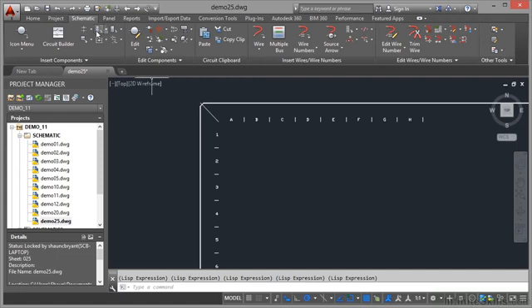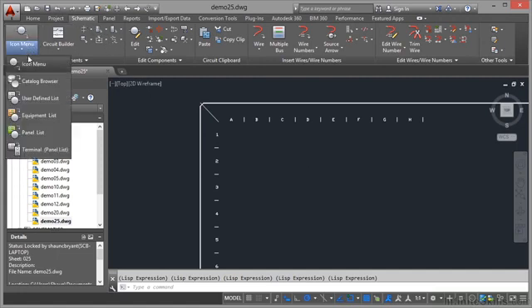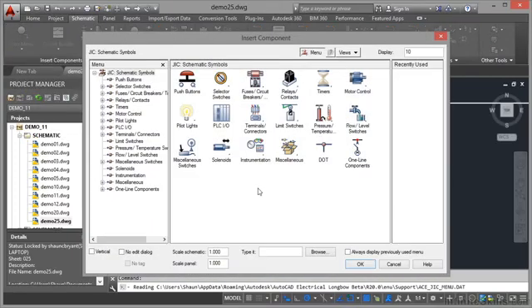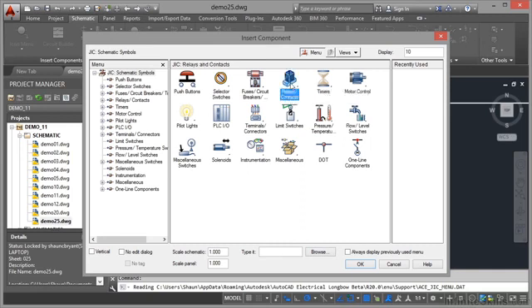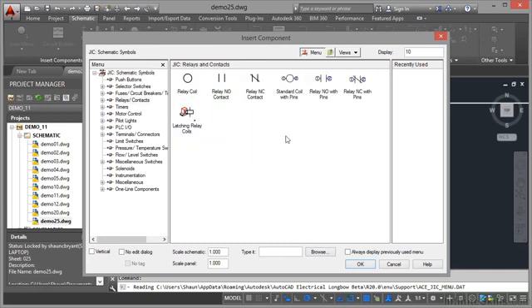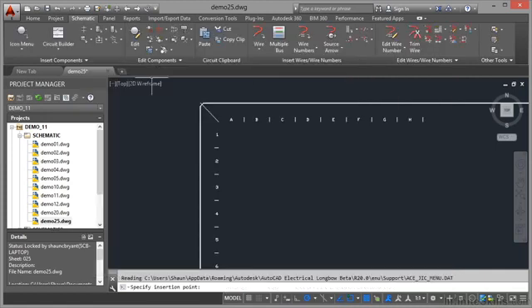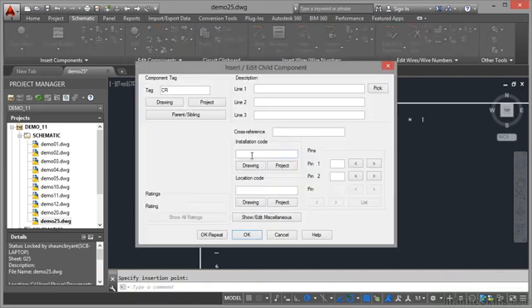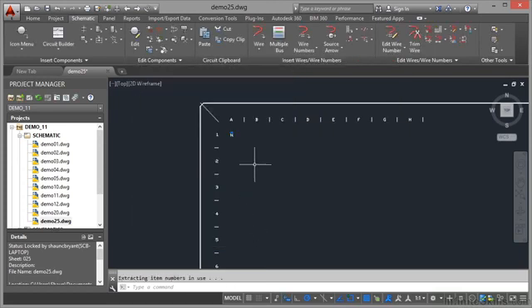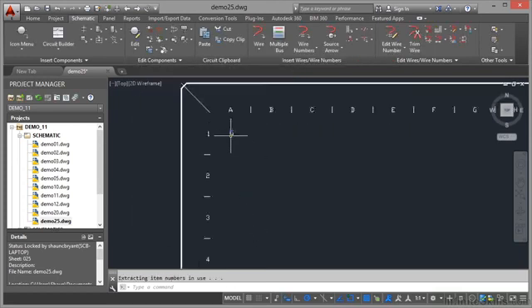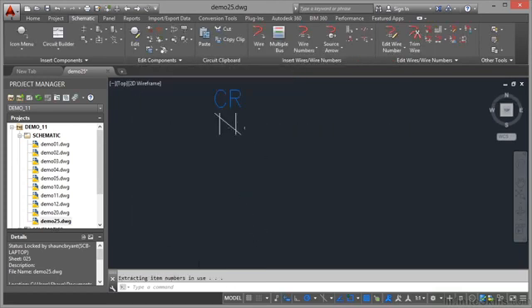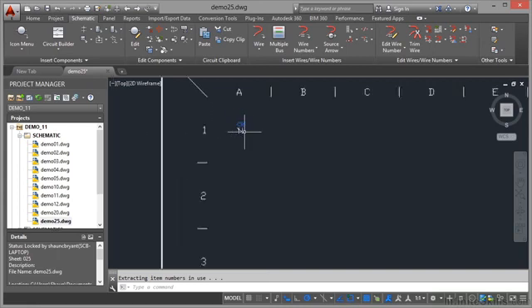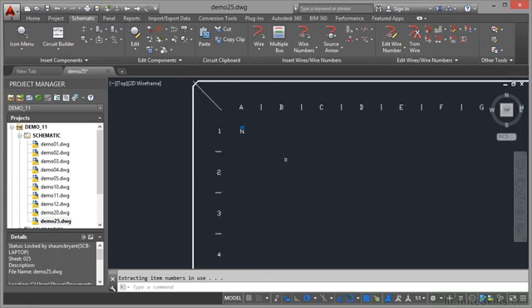I'm going to go to the schematic tab on the ribbon and then click on the icon menu and this will bring up all of the icons, the schematic symbols that I can place inside my drawing. So let's go for something simple like a relay or a contact. So if I click there I'll go for let's say a relay. So you've got normally closed or normally open NC or NO. So let's go for a relay normally closed contact that one there and I'm going to place it let's say in that A1 area there so that will update everything there. There's the tag, I'm just going to OK that.